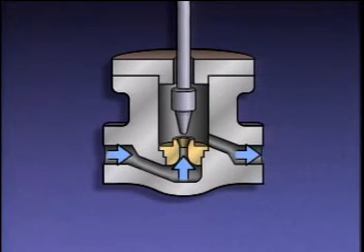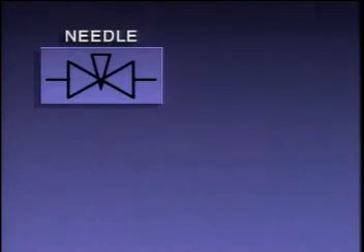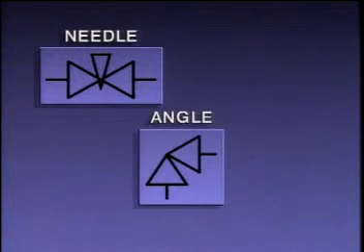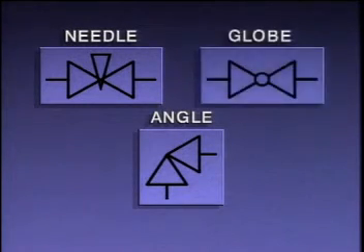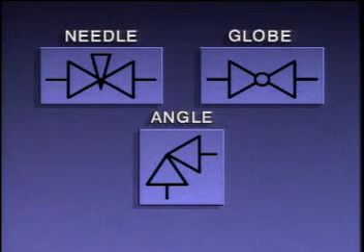A small movement of the stem causes a small gradual change in the flow rate through the valve. This gives the needle valve an extremely fine throttling ability. On a piping system diagram, a needle valve generally looks like this, an angle valve generally looks like this, and a globe valve generally looks like this.